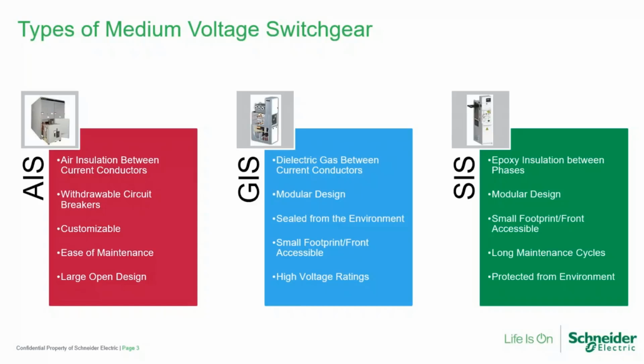This is much more true in the utility side of the business. But as of the past decade or so, gas insulated switchgear has become much more prevalent in a handful of power critical markets, even in the industrial side and even in the heavy commercial side of the US. And we'll talk a little bit more about the advent of gas insulated switchgear. But the largest difference is that the main insulating dielectric, or the main insulating material used in gas insulated switchgear, is some kind of pressurized gas. Whether that's the more traditional SF6, and we'll talk a little bit more about what that is, or a newer dielectric gas being used.